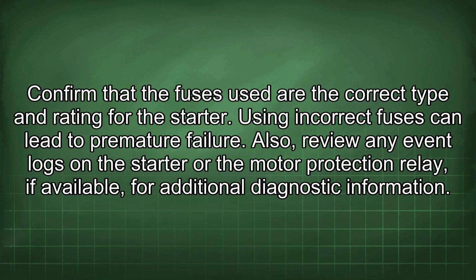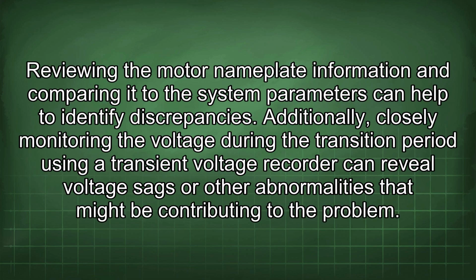Also, review any event logs on the starter or the motor protection relay, if available, for additional diagnostic information. Reviewing the motor nameplate information and comparing it to the system parameters can help to identify discrepancies. Additionally, closely monitoring the voltage during the transition period using a transient voltage recorder can reveal voltage sags or other abnormalities that might be contributing to the problem.